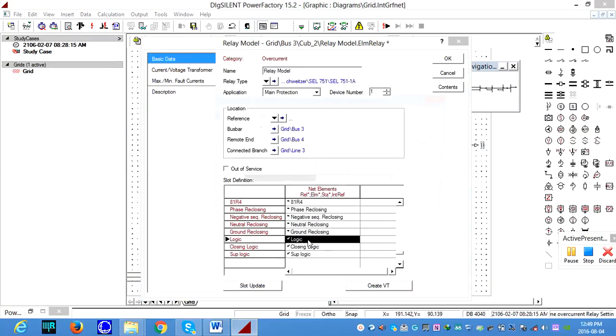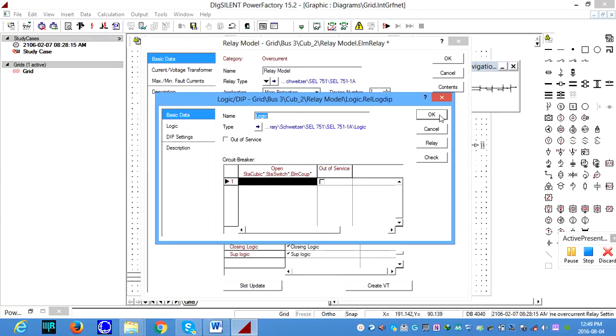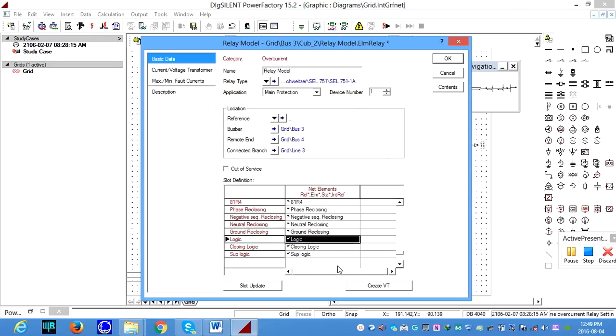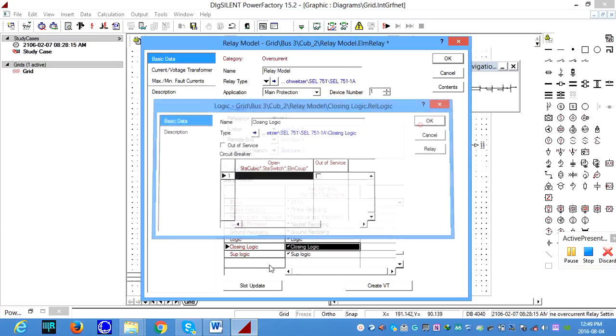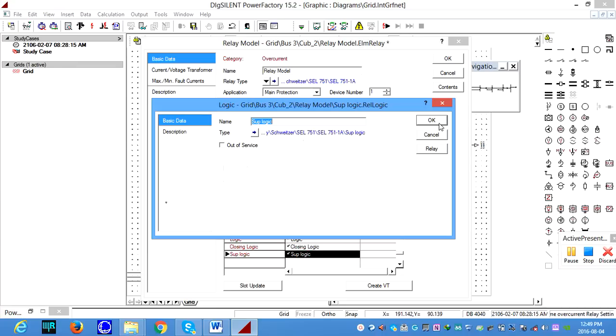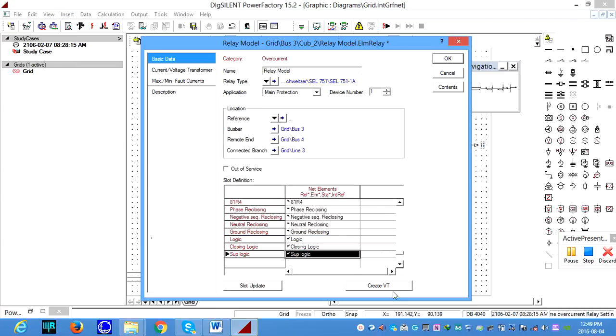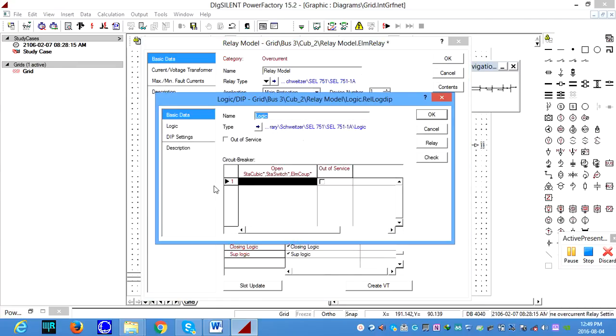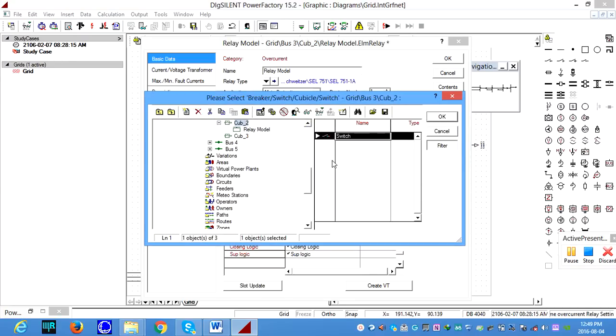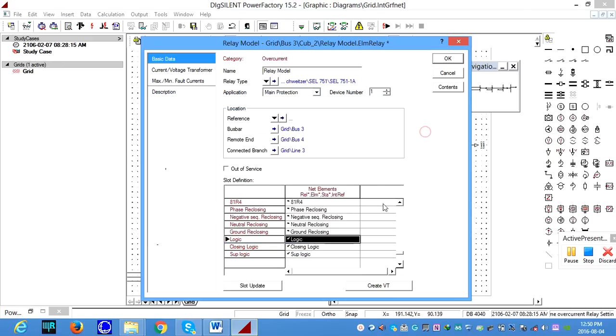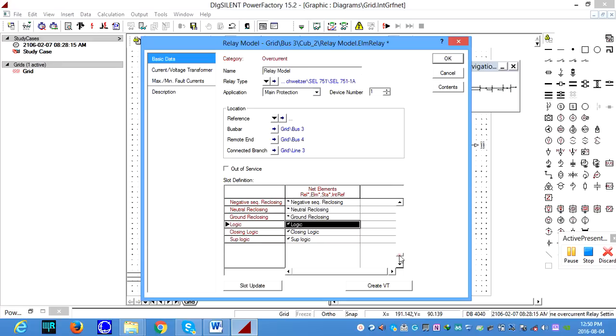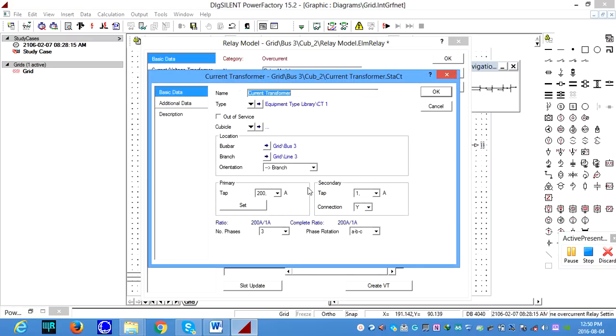And the logic, I think in DigSILENT we don't worry about that. It is already built in, so we are happy about that. Closing logic also, we can leave it as it is. Settings will find the specific cubicle. But in the logic, if the breaker is tripped, this relay gives a tripping signal to the breaker, and if you want to configure it to a specific switch, you can. But in this case, it will select automatically, so we leave it. I'm just sharing this knowledge. Okay, coming to the review of the protection settings, especially for the overcurrent, phase and ground elements, we make sure the current transformer is 200 to 1 amps.